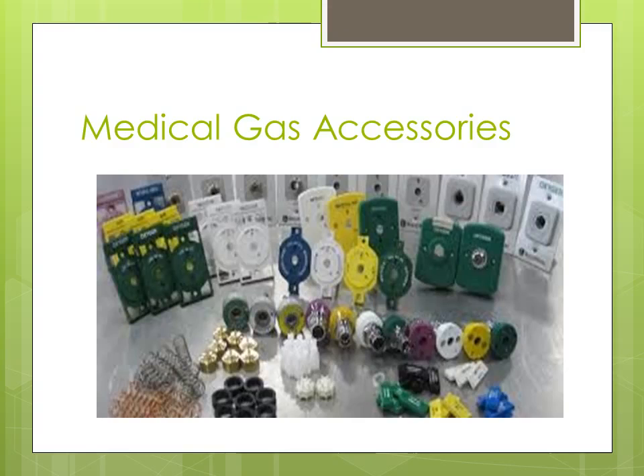Just another picture of different accessories as it relates to medical gas. I just saw this image, and you see all kinds of different things here. One of the things you see down here is some springs and some O-rings and some other pieces and parts. These are rebuild kits that you might use to rebuild an outlet. I just thought this image would be interesting for you to see.